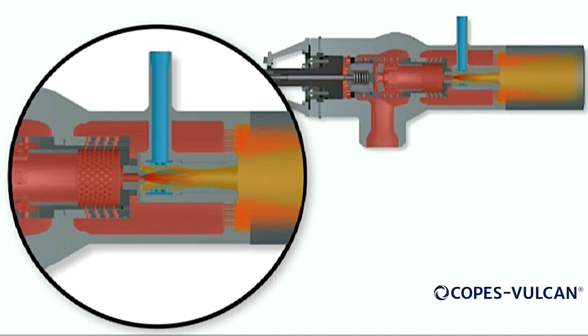Steam atomization has several benefits over mechanically spraying the cooling water via nozzles. Mechanical spray nozzles, even spring-loaded types, are limited in their turndown as the water atomization and spray pattern degrade as the water flow rate and available pressure differential reduces.